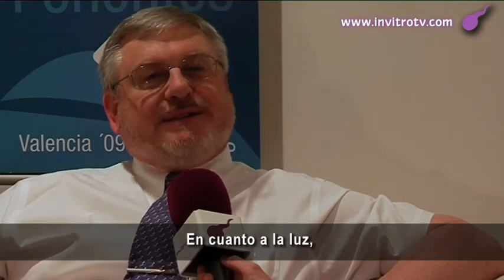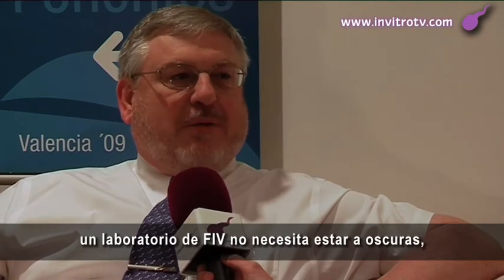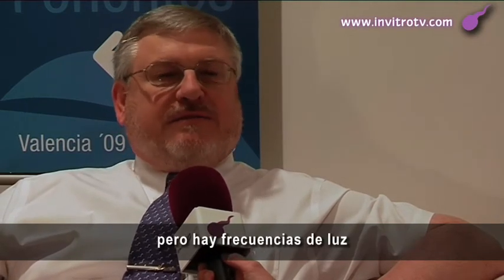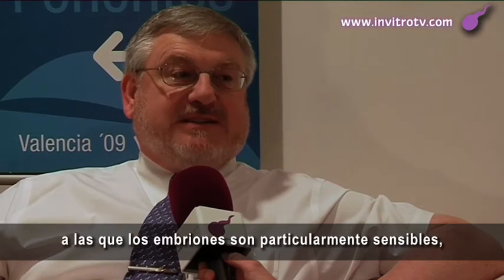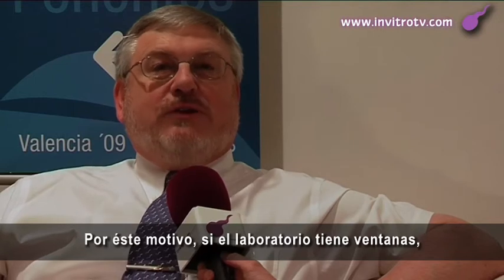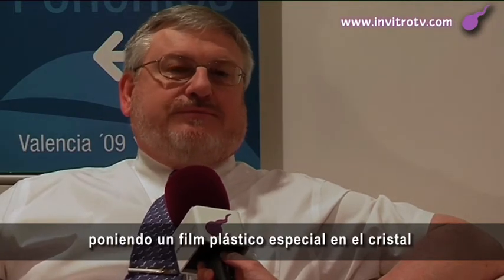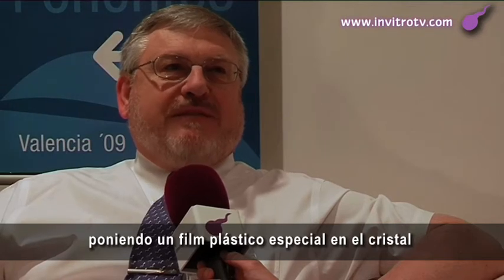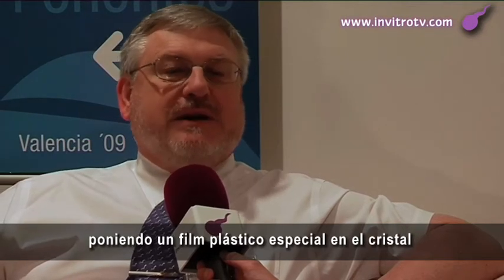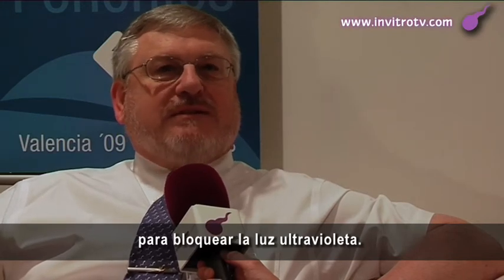With regards to light, an IVF lab does not need to be dark or pitch dark. There are certain frequencies that embryos are particularly sensitive to, in particular ultraviolet. So if you have windows, some people will make the windows all black.